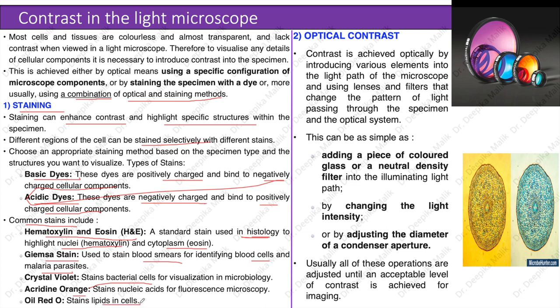Optical contrast is achieved by introducing various elements into the light path of the microscope and using lenses and filters that change the pattern of light passing through the specimen. This can be as simple as adding a colored glass or neutral density filter into the illuminating light path, changing the light intensity, or adjusting the diameter of the condenser aperture. Usually all of these operations are adjusted until an acceptable level of contrast is achieved for imaging.